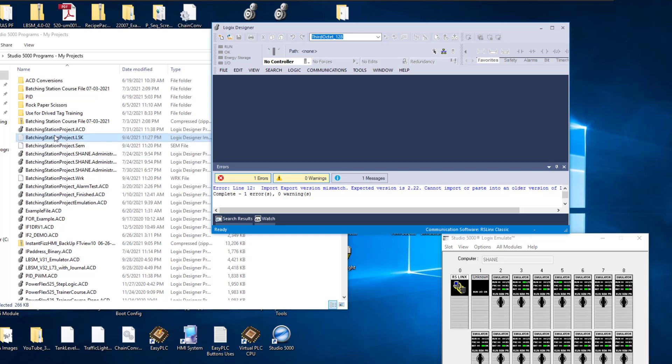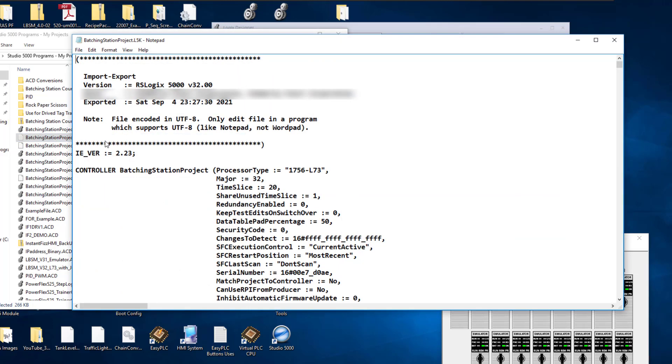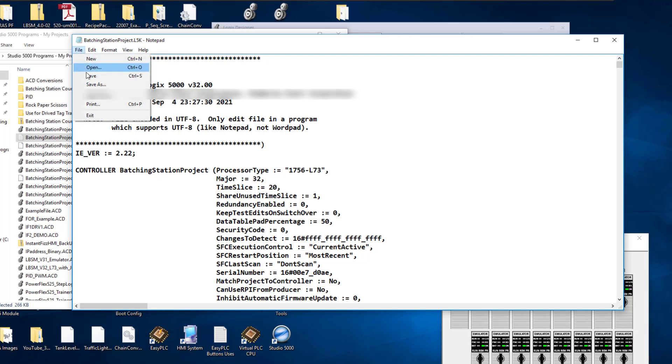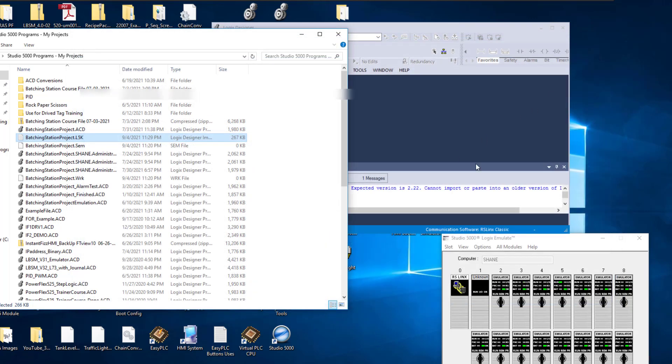So we're going to open up our L5K file. We're going to change this version, this IE underscore version. We're going to change that to 22. We're going to hit save.